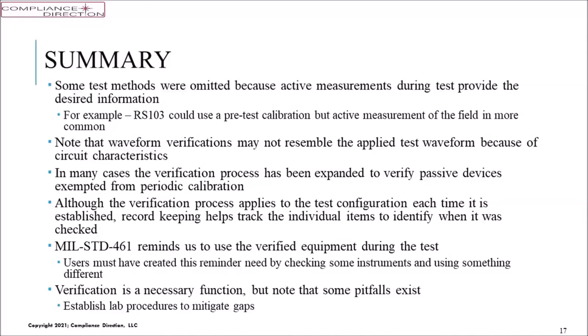Waveform verifications don't resemble the applied test waveform. Circuit characteristics, parasitic elements, cable placements, coupling, all kinds of things distort the waveforms. So when we measure the test waveform, it won't have the same appearance as our calibrations. In many cases, the verification has been expanded just to verify these passive devices that have been exempted from the periodic calibration. This verification process applies to the configuration each time it's done. Record keeping helps track when we did the last things.